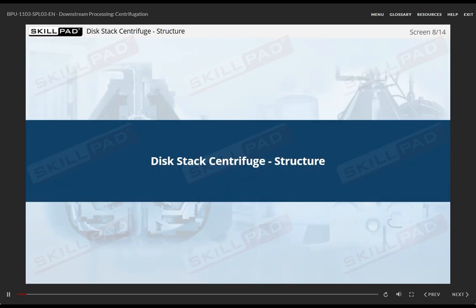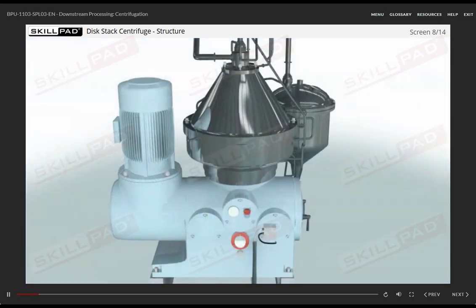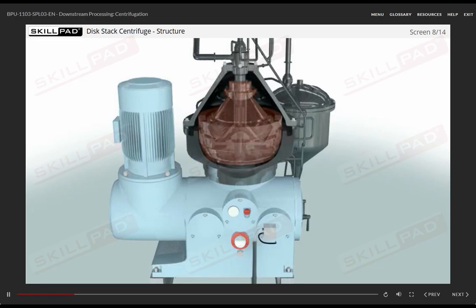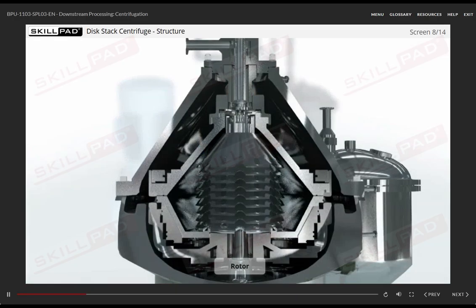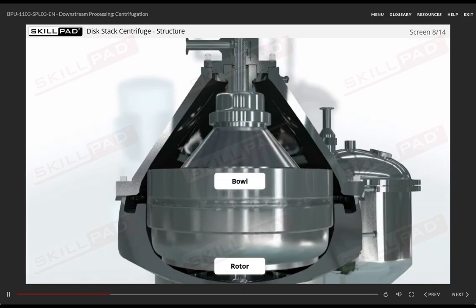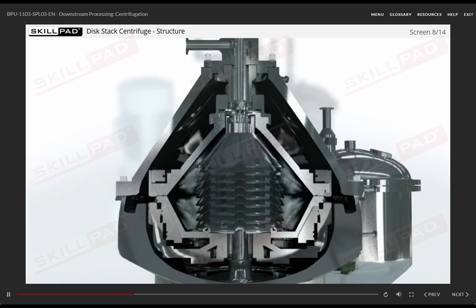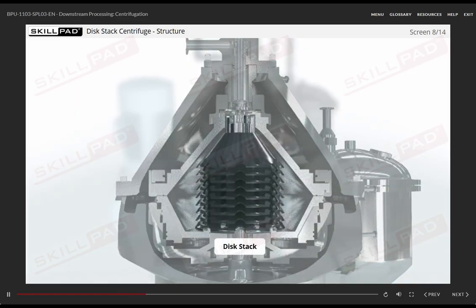Disc stack centrifuge structure. Let's examine the main components of a disc stack centrifuge. The separation process takes place in a bowl. The central rotor is attached to and surrounded by the bowl, which rotates at high speeds during operation. The bowl also contains the disc stack. This consists of a number of conical plates placed one on top of each other at a fixed distance.